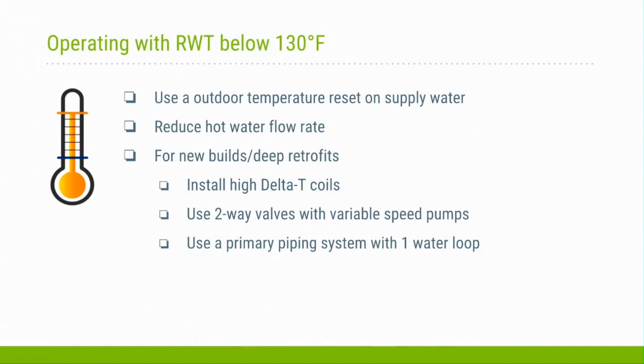You can also reduce the hot water flow rate. It's another way to get at that same approach. And then for deeper retrofits or new builds, a couple of big considerations are high delta T coils. With your typical coil, you have a supply water temperature of 180 and you get back 150. You can get coils that are designed to have a delta T of closer to 60. So even when you're supplying your hottest water, you'll be getting back return water that will allow the boilers to operate in condensing mode.